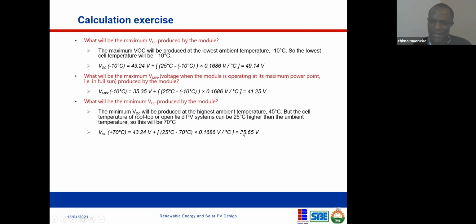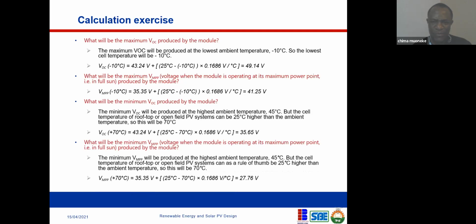The minimum is 35. Now let us calculate the minimum voltage at the maximum power point. We also use 70 degrees centigrade, but here we use the voltage at the MPP, which was given as 35.35. When you do that, you get a voltage of 27.76 volts.